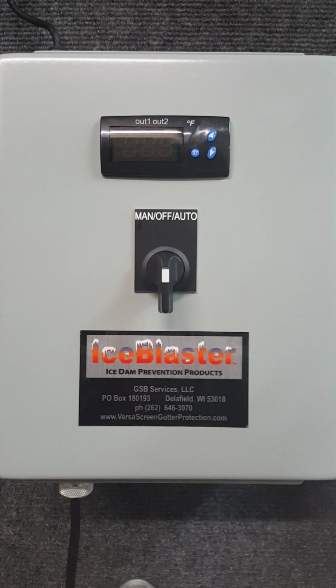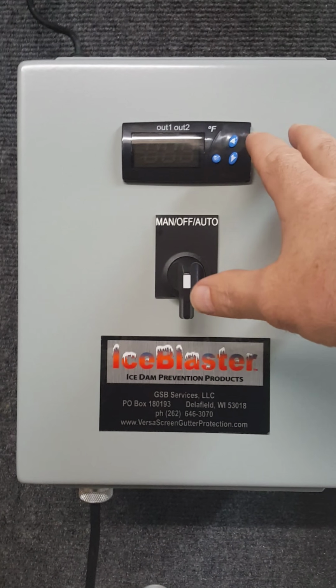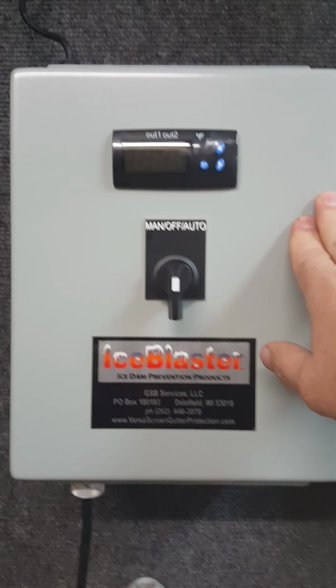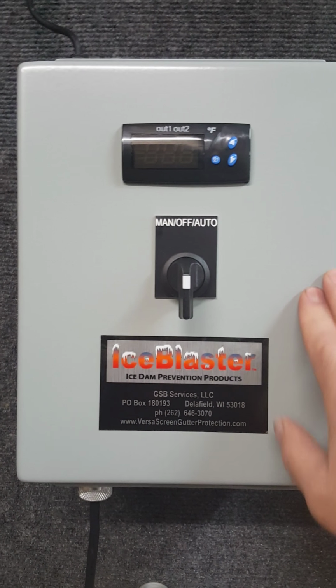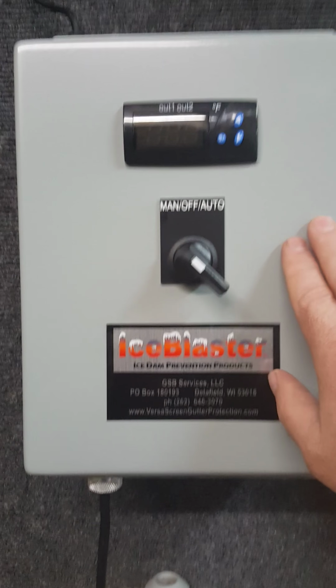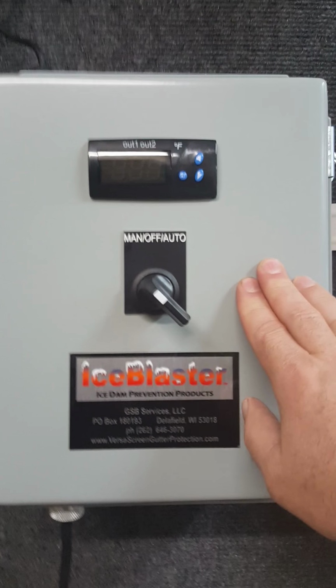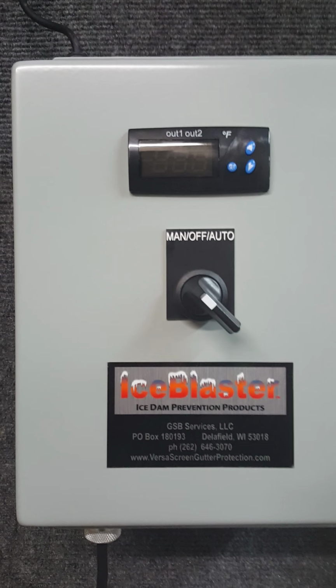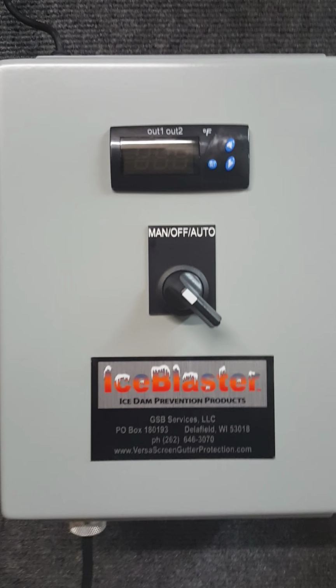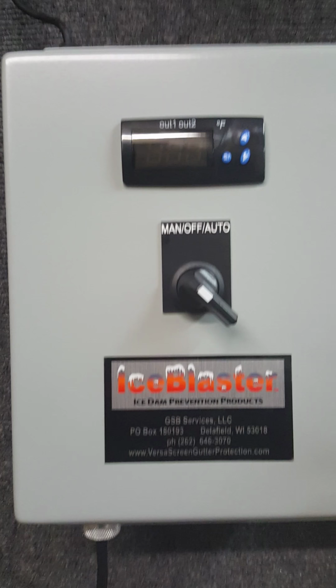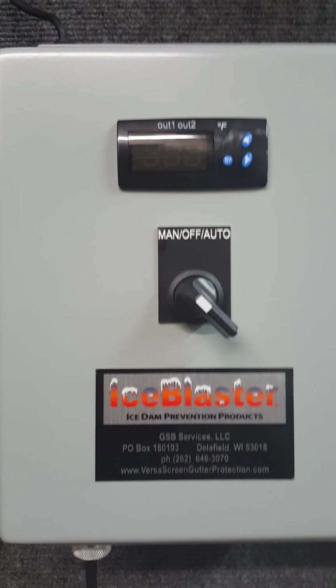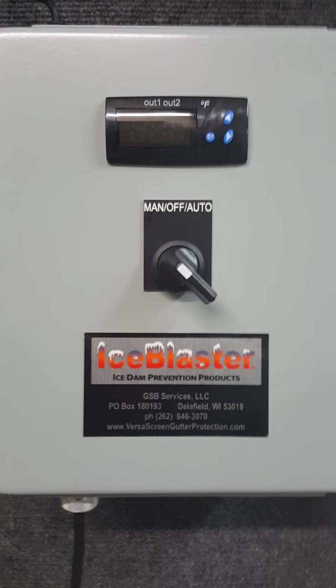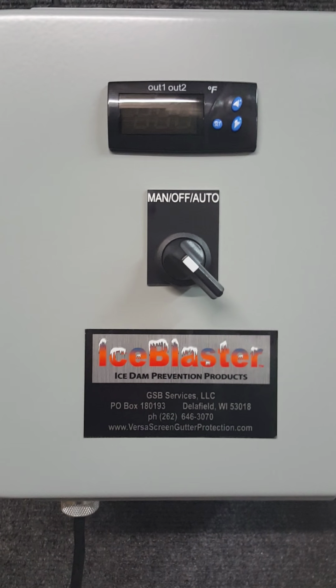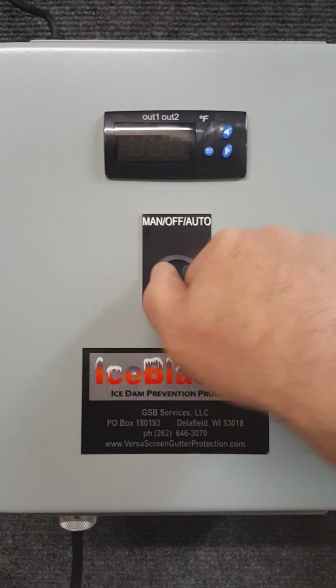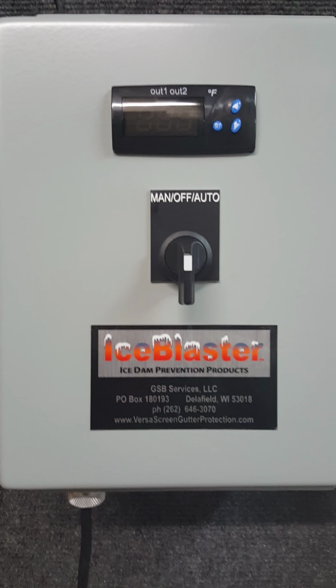So as we look at our panel, you notice all of the things on the outside. It's very easy to operate, very easy to get the feedback to know what's going on. It's got a 3-position rotary selector switch. The first position on it is manual. When you turn it to manual, nothing's going to light up on our control panel because all it's doing is flipping a switch on the inside of the panel. It's closing a contactor so that all of the incoming power can flow to the heat cables themselves. So in effect, it turns the heat cables on. It's just like a very powerful on-off switch, and it can be used that way under some circumstances.